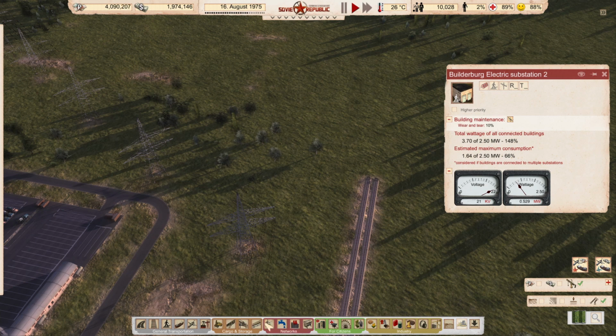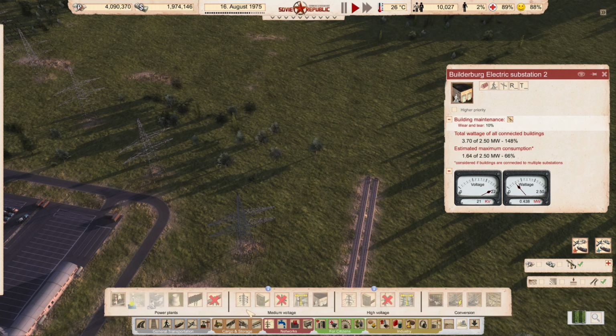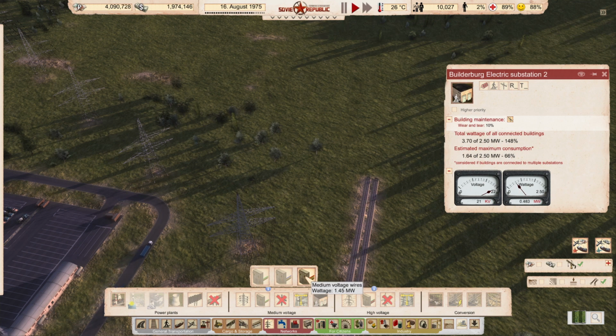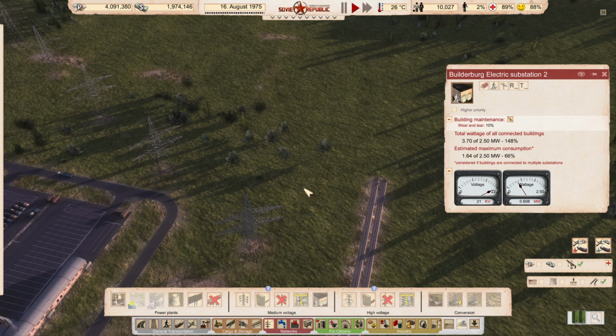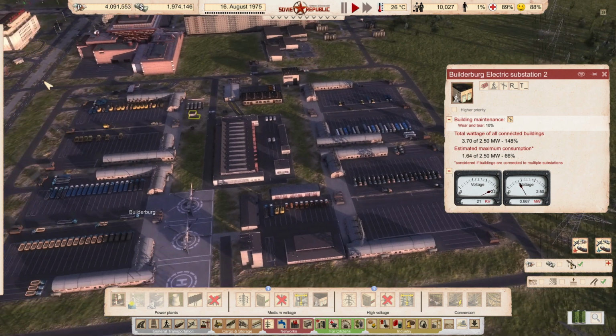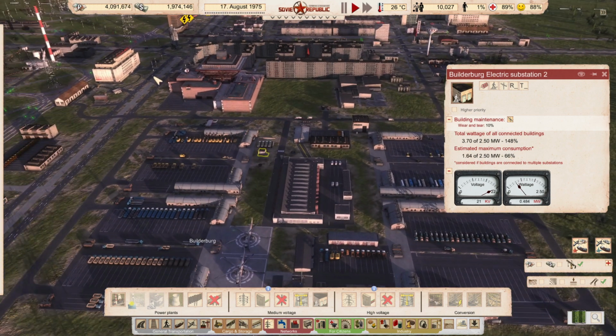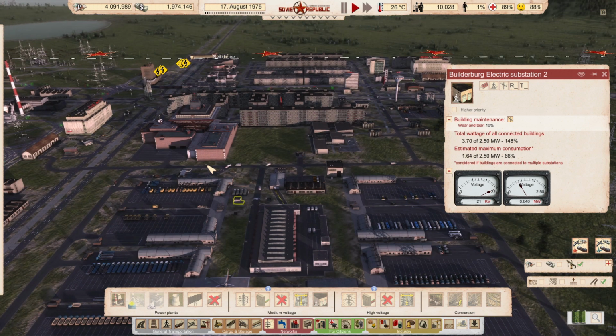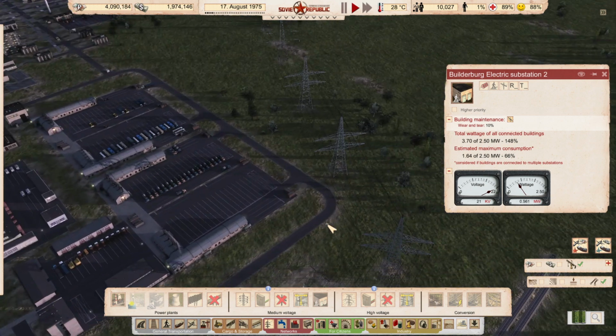However, if you look at the underground lines, the highest one only provides 1.45 megawatts. We're already over that, and that's with the system only at 66% capacity. So we're already stressing the system, drawing more power through those lines than they're supposed to have, which can cause brownouts throughout here.